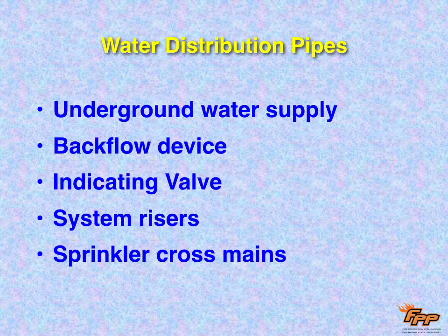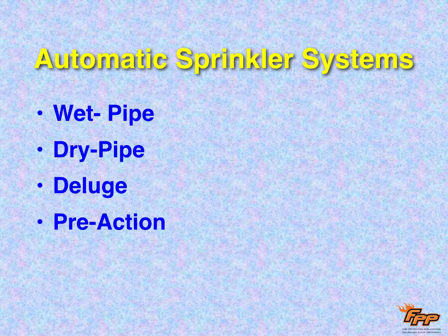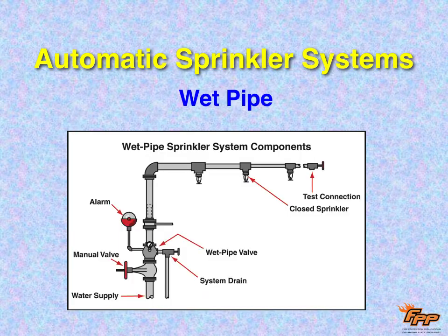From there, there's going to be a riser that comes out of the ground with all of the devices and pressure gauges that the fire inspector needs to see. Then from there, it'll go up into the ceiling area, and there'll be plumbing cross mains and branches that go to each one of the sprinkler heads. There are four kinds of sprinkler systems: wet, dry, deluge, and pre-action. Now, if you're a genius, you might have already figured out a wet pipe system. Yeah, it's wet. It has the water already in it. So in wet pipe sprinkler systems, there's water in the plumbing all the way to the sprinkler heads.